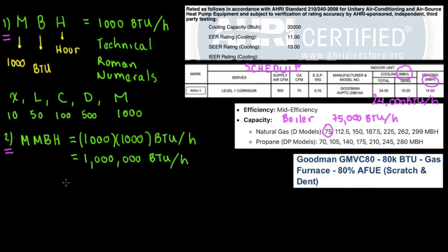All right. Now let's talk about number 3. What is BTUH? This is pretty much BTUs per hour, not times hour. For example, if we're selecting equipment that has been tested by the AHRI standard, usually you get a certificate, and in this case the certificate says cooling capacity in BTU hour.